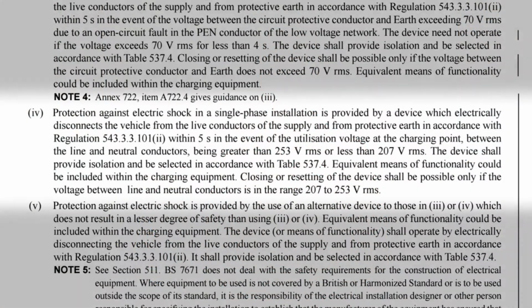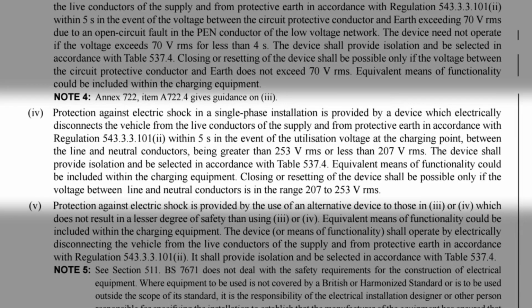Indent 4 reads, protection against electric shock in a single phase installation is provided by a device which electrically disconnects the vehicle from the live conductors of the supply and from protective earth in accordance with regulation 543.3.3.101(ii) within 5 seconds in the event of the utilisation voltage at the charging point between the line and neutral conductors being greater than 253 volts or less than 207 volts. The device shall provide isolation and be selected in accordance with table 537.4. Equivalent means of functionality could be included within the charging equipment. Closing or resetting of the device shall be possible only if the voltage between line and neutral conductors is in the range 207 to 253 volts RMS.